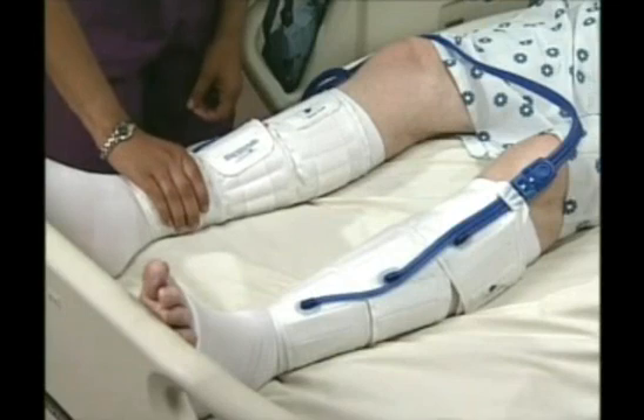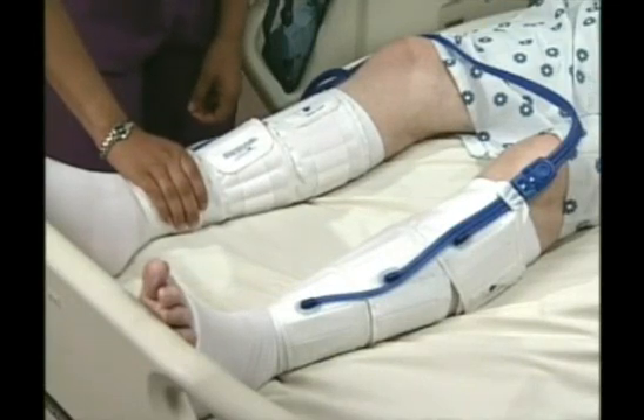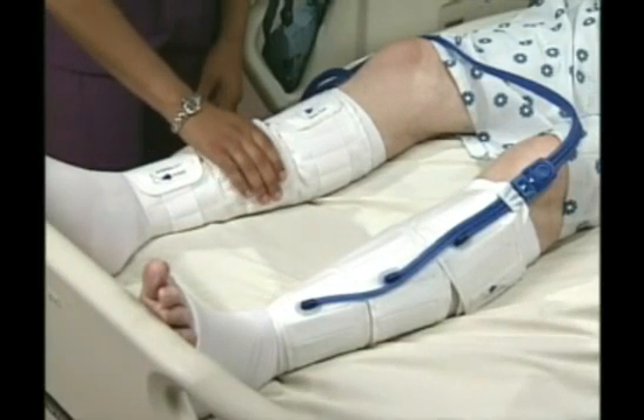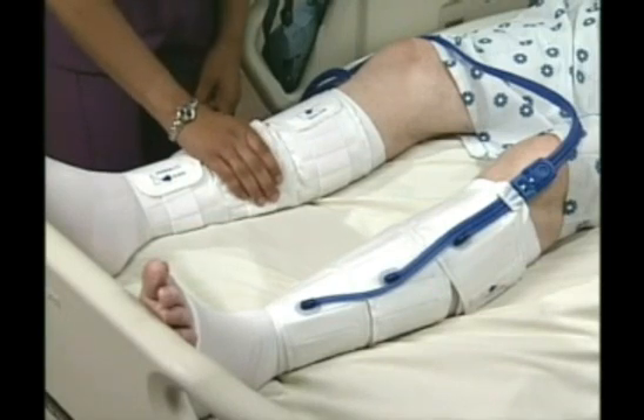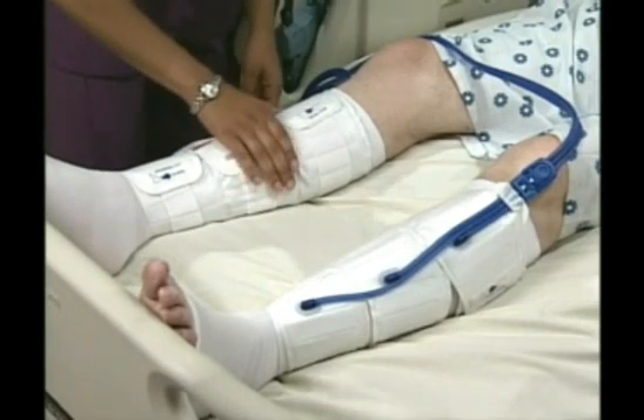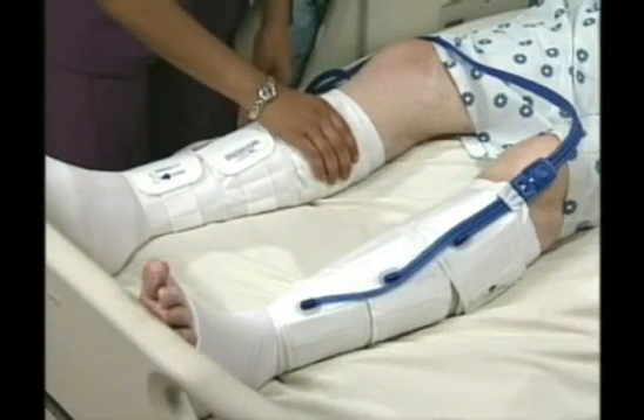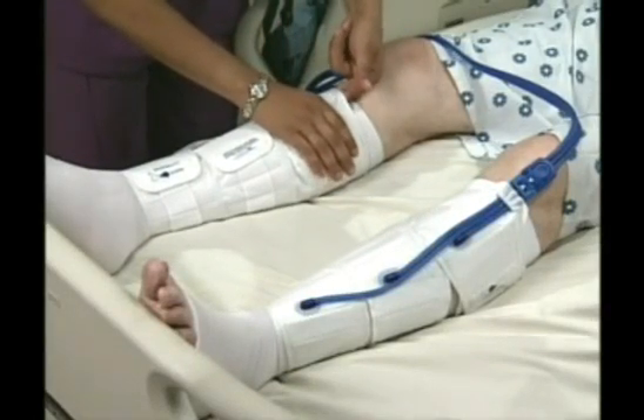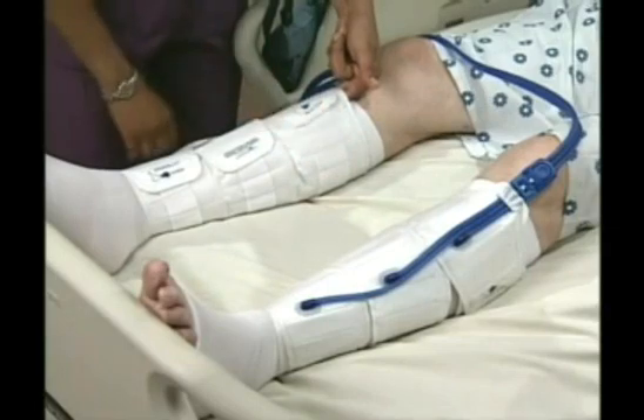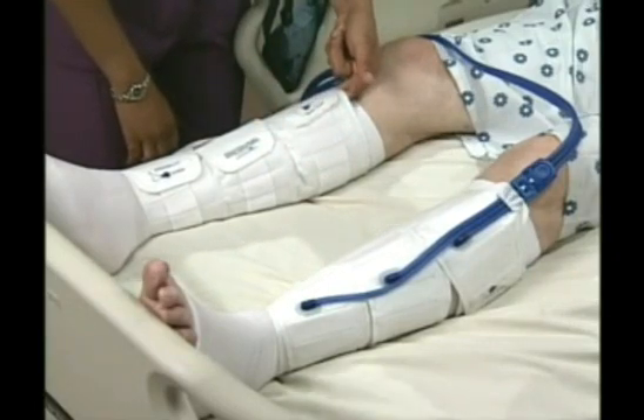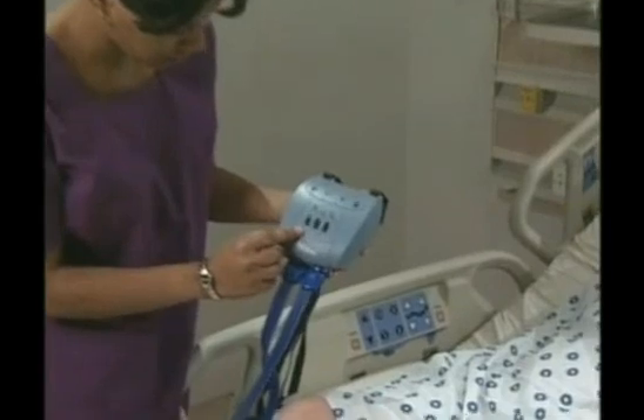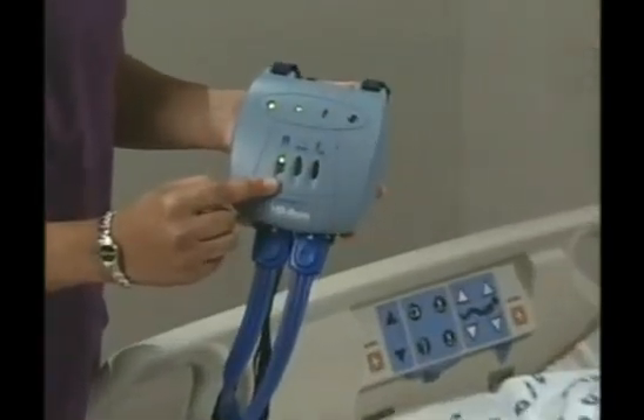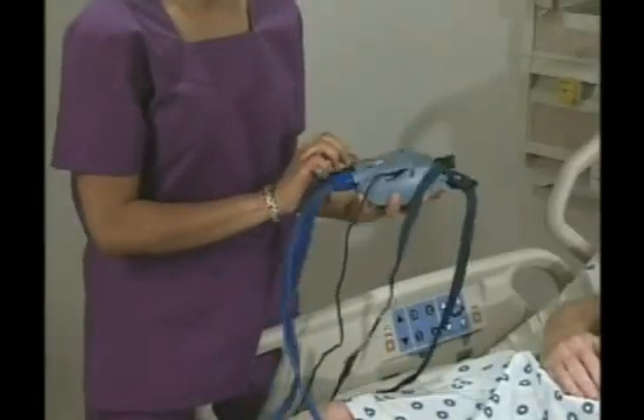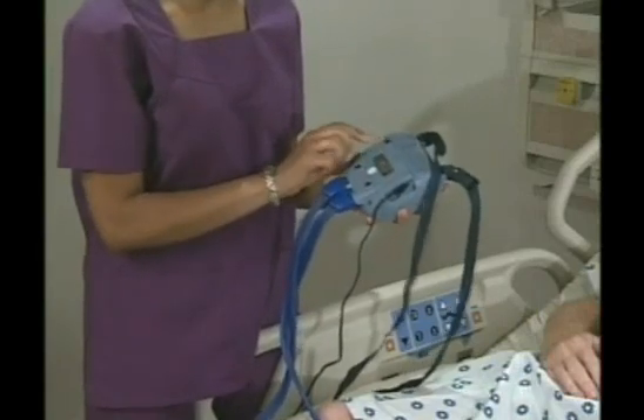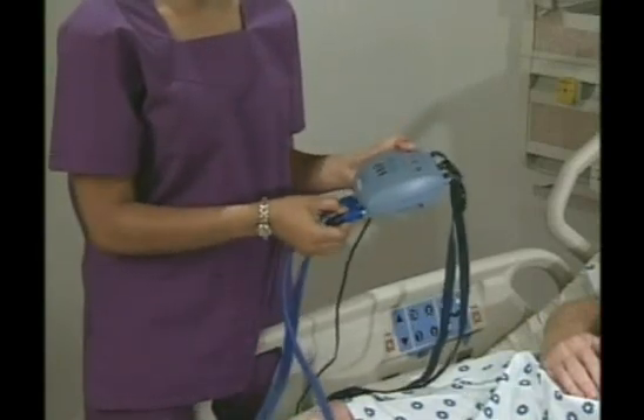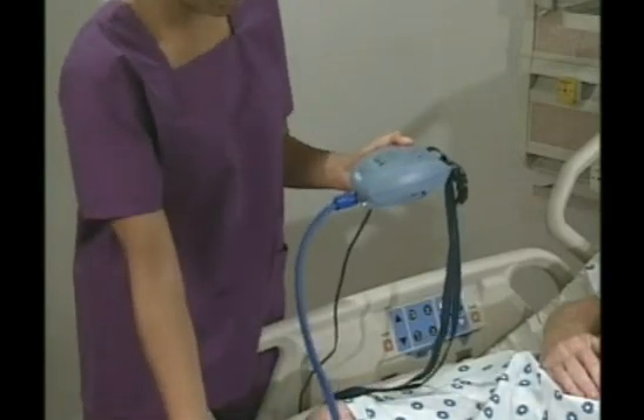During the first cycle, carefully monitor at least one complete inflation-deflation sequence on each leg, checking to make sure that the cells are inflating and deflating in the correct sequence from distal to proximal. You should still be able to place 1 finger between the sleeve and the patient's leg during the inflation phase of the cycle. Finally, check to make certain that the correct operation mode is indicated. To change the mode of operation, simply switch off the control, connect the appropriate sleeve, and switch the device back on.